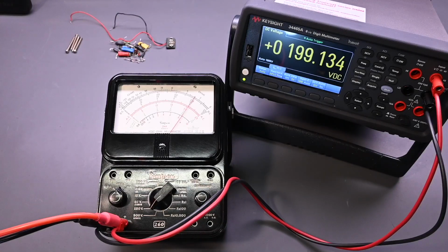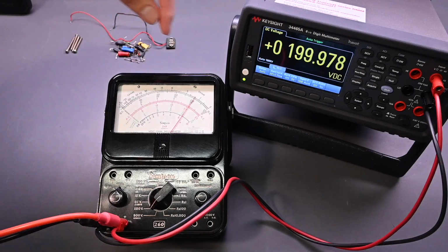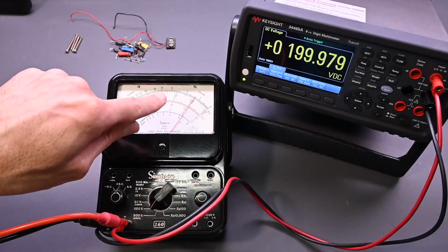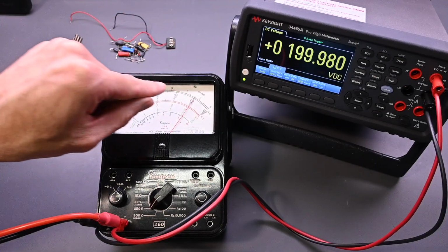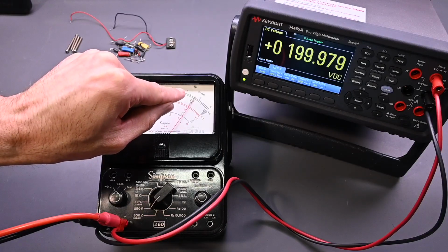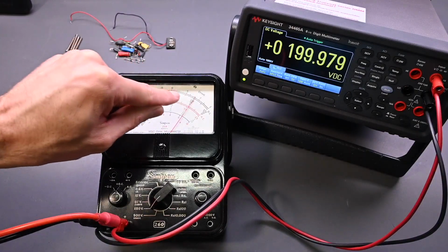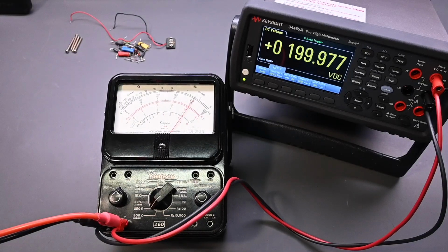So that should be getting close there to about 200 volts. Yep. Because this has an adjustment knob, it's a multi-turn adjustment, but it's a little bit touchy to dial numbers in, but that's very close to 200. I'm going to say that's close enough. And yeah, right there, 200 volts. So to my eye, it's just a little bit over the 200, maybe one tick mark over. It's reading just slightly high, but that's within spec. I wouldn't be worried about that. That looks okay. It's very, very close. So no problems there.